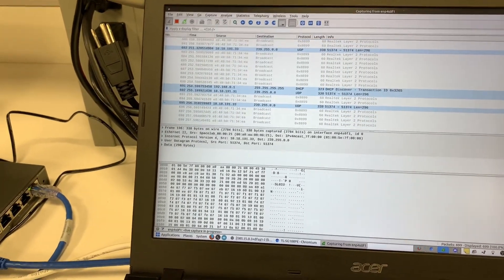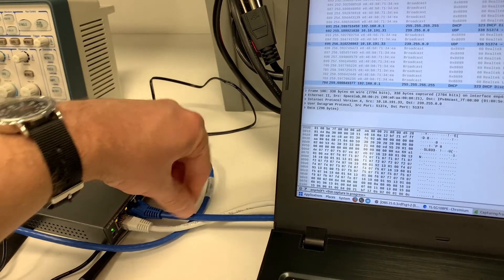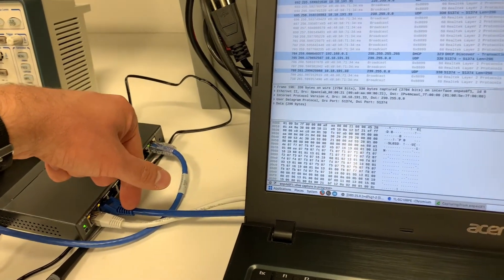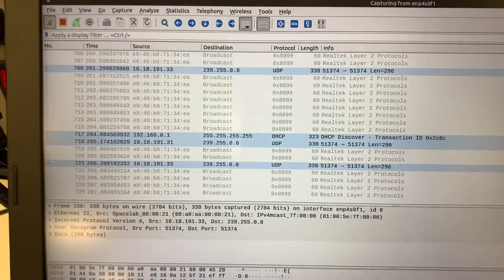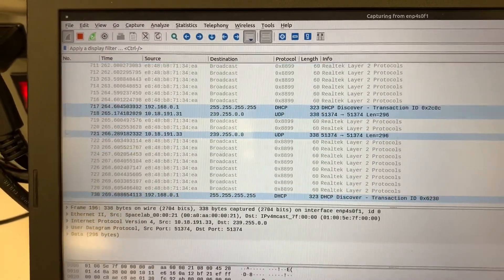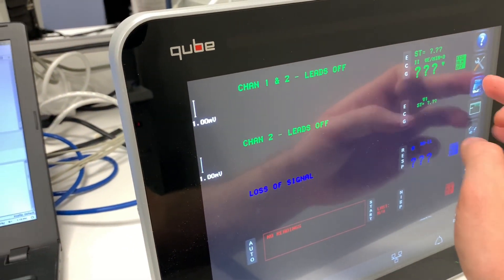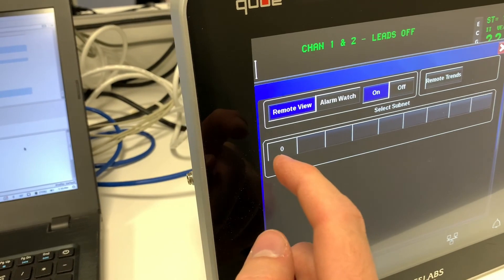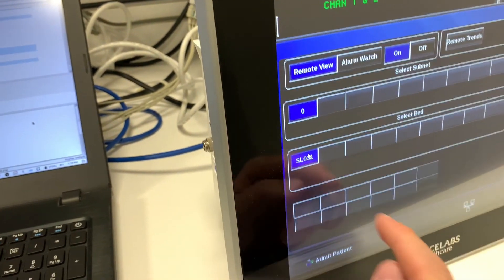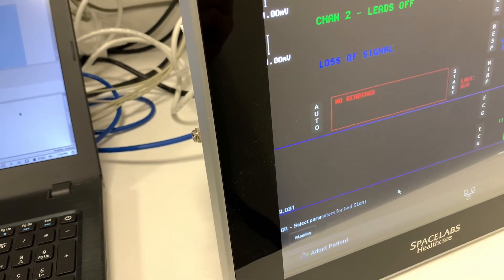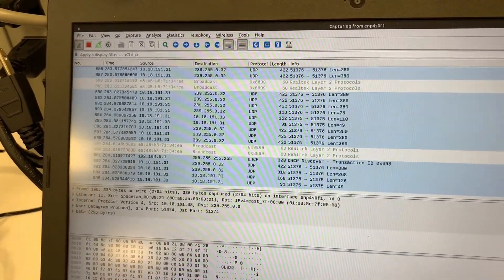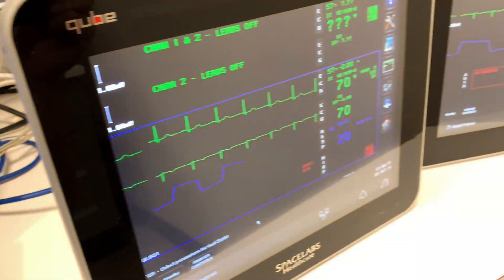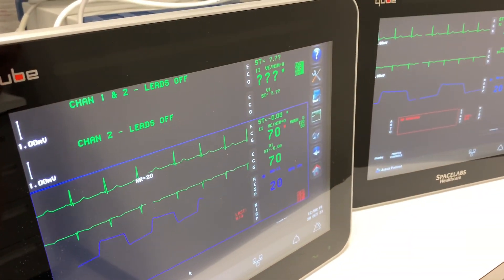And there's some things you can do to experiment. For example, I unplugged and plugged back in ECG number two. So the connection between these two was interrupted. And you can see the traffic between them has dropped off almost entirely. Now if I go back to this ECG here and pull up the remote trends again, and select full bed view, you can see the traffic really starts taking off between the two devices again as it's pulling the trend information.